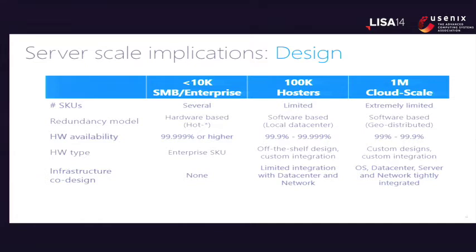So the numbers here I'm putting is maybe about 2 nines. Electric utility power from the utility is somewhere between 2 nines and 3 nines. So if you can design it to be around that number, then you essentially are tied to the base things that you cannot control. The utility comes from somewhere else. The rest you have to deal with by doing balancing in software. So that's another design point to consider.